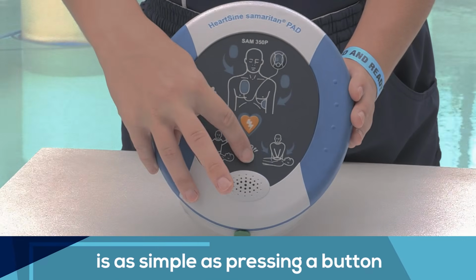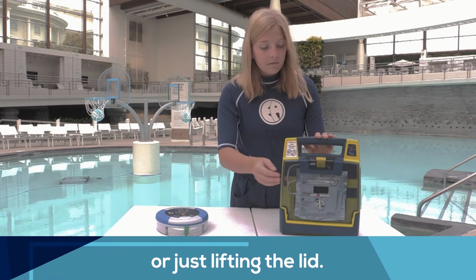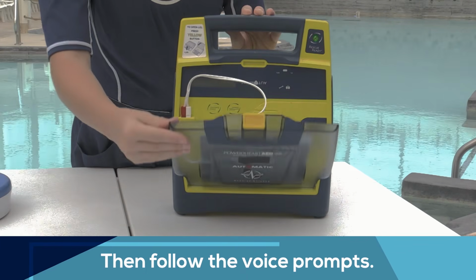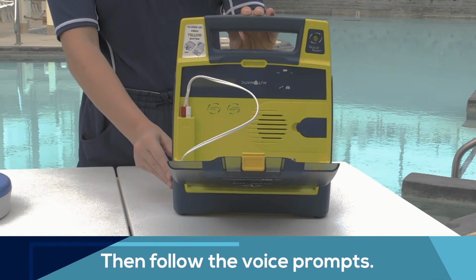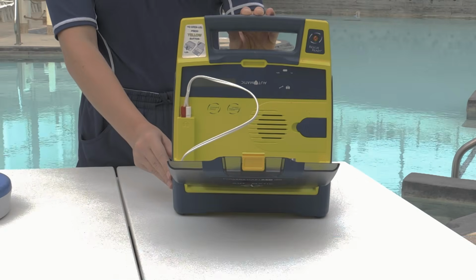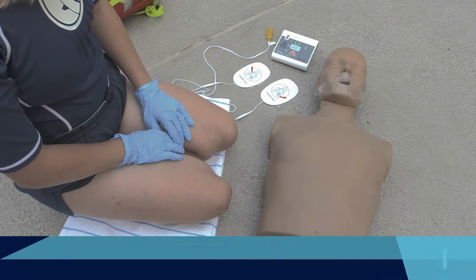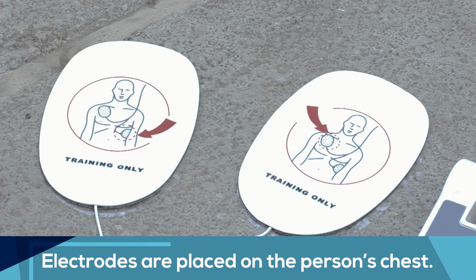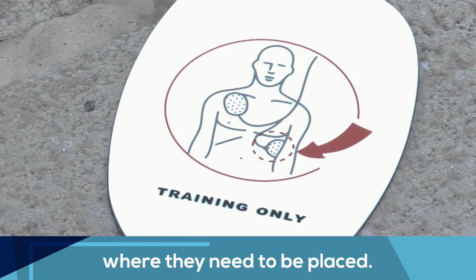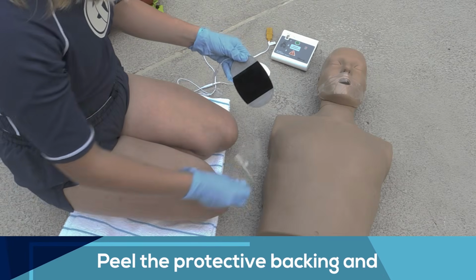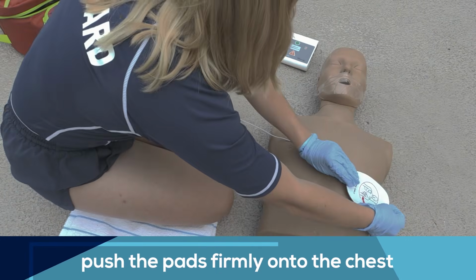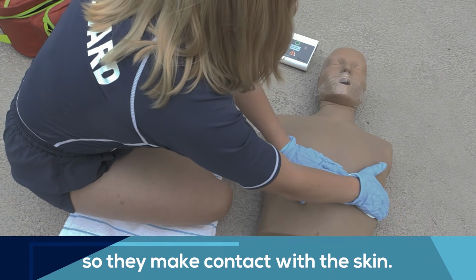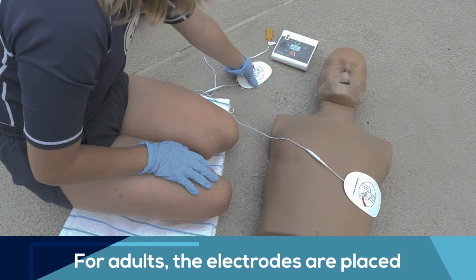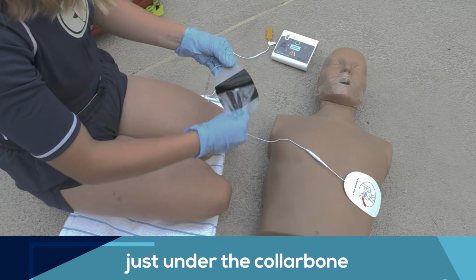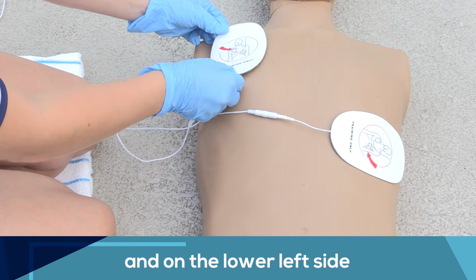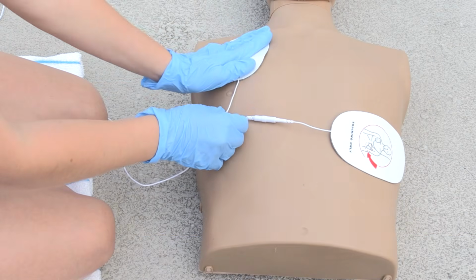Turning the device on is as simple as pressing a button or just lifting the lid. Then follow the voice prompts. Apply pads to patient's bare chest. Electrodes are placed on the person's chest. Images on the electrodes show where they need to be placed. Peel the protective backing and push the pads firmly onto the chest so they make contact with the skin. For adults, the electrodes are placed on the upper right side, just under the collarbone, and on the lower left side along the lower ribs.